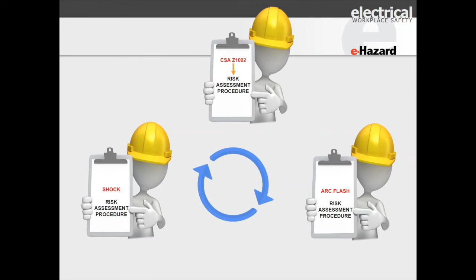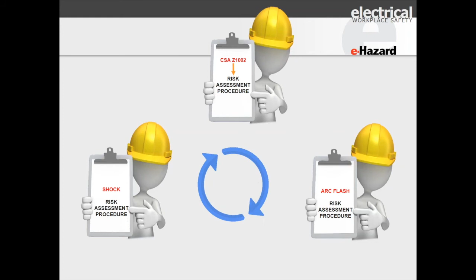So just to sum up a little bit then, CSA Z1002, the risk assessment procedure, was benchmarked for CSA Z462. We did not want to reinvent the wheel, and we used those technical experts on risk. If you look in Z462 or NFPA 70E, what you're going to find is a shock risk assessment procedure, which is based on the 3 steps. You're also going to find basically 2 levels of arc flash risk assessment procedure. One of them is to use the PPE category method, the classic tables in Z462 if you are within the correct parameters. The other one is the incident energy analysis risk assessment procedure.